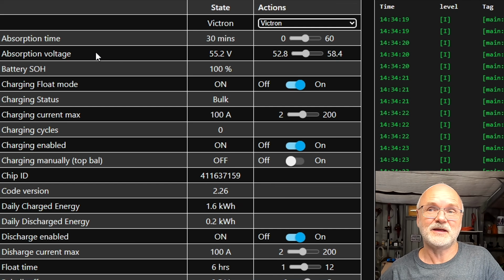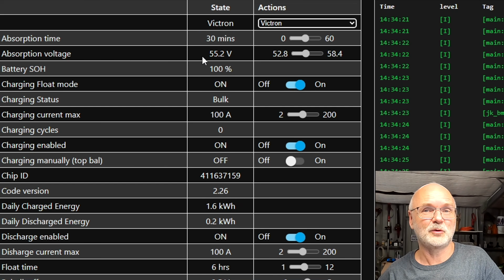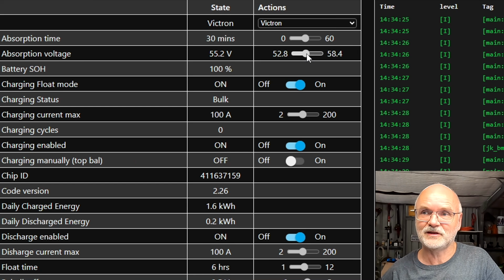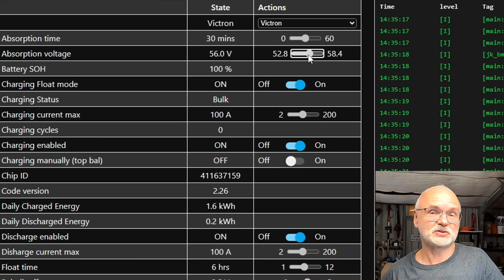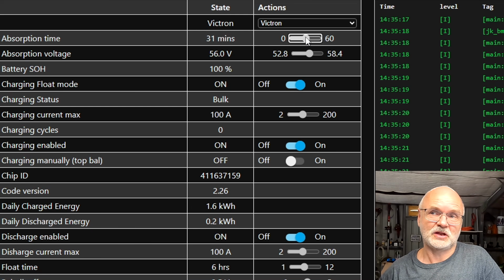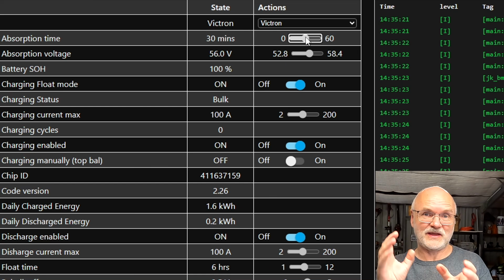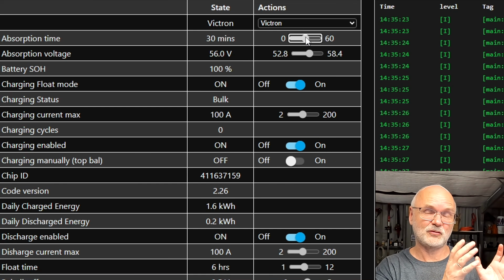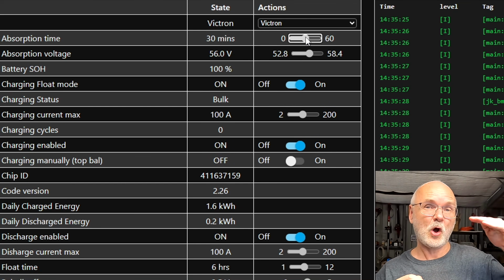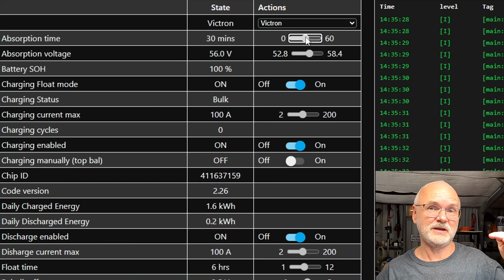We can see an absorption voltage of 55.2 volts here, which I can change. I click on the slider and use the left-right keys, so I can set my absorption voltage to 56 volts, for example, with an absorption time of 30 minutes. I can change this as well, and this information would be sent to your inverter. So it charges now to 56 volts and will hold the voltage there for 30 minutes.